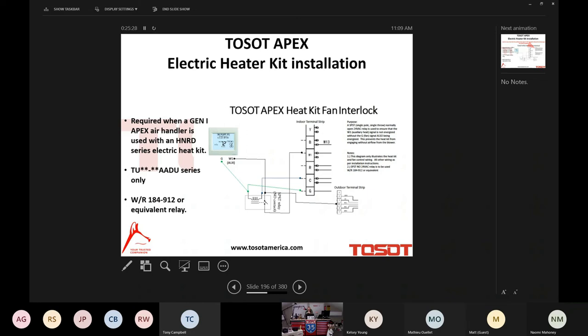A White-Rodgers 184-912, or equivalent relay. This relay will not allow the electric strip to operate without the indoor blower operating. Make sense? Yeah, there's a potential issue if the electric strip is energized and we're not blowing air, right? So simply that's what this is utilized for. And Wes and Dennis King, one of our other Tosot gurus, came up with this wiring diagram and this option for us.